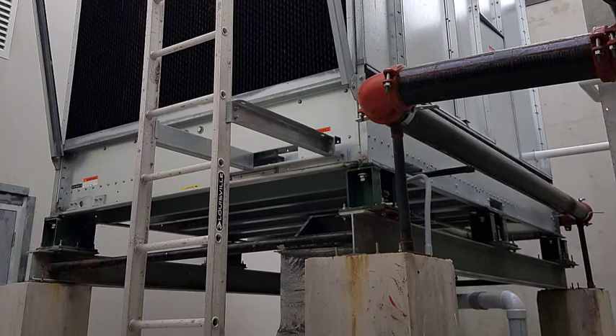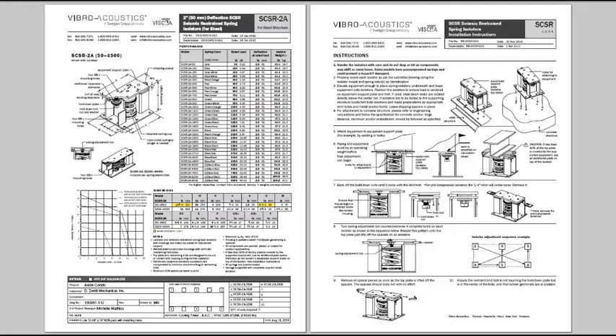is about 10,330 pounds. As an interesting side note, originally CSR isolators had been quoted and selected, but were then replaced with SCSR isolators due to their inherent higher strength for resisting lateral loads from wind and seismic forces. This project was exempt from seismic requirements, so it was only wind loads that were of concern.